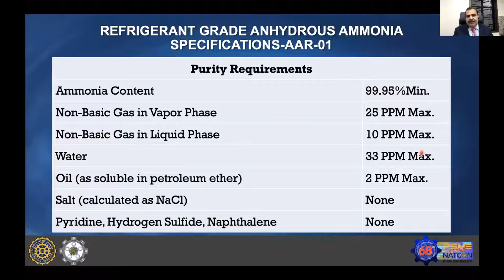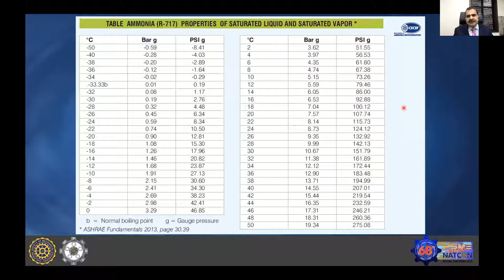This is a pressure temperature chart. I'm sure you're well aware of it. I'm just showing that our refrigeration system is totally dependent on this pressure temperature chart. All the system design calculations are totally dependent on it. So water and the non-condensable gases, mostly air but along with that nitrogen, hydrogen, hydrocarbons, they all affect the performance of a refrigeration plant.